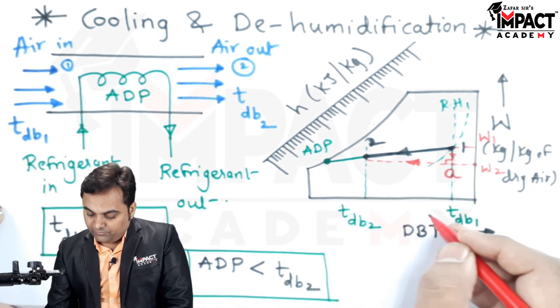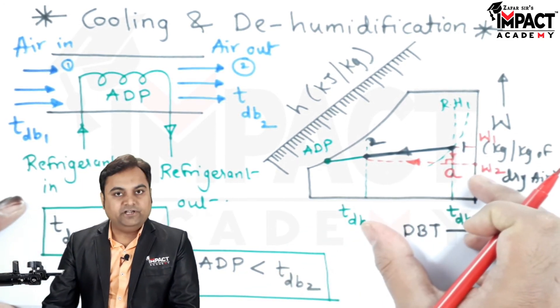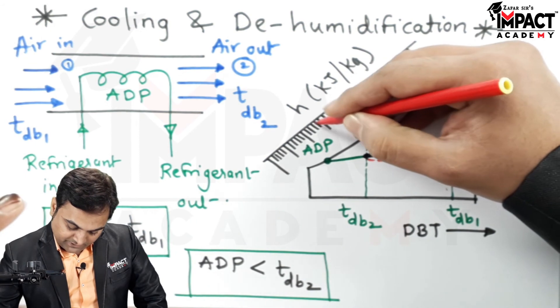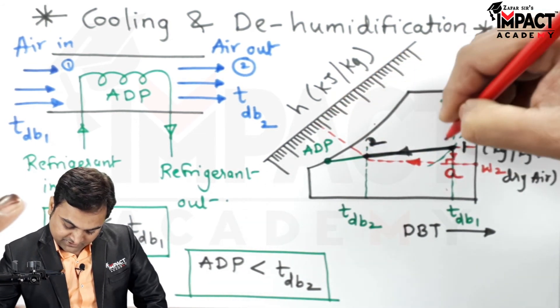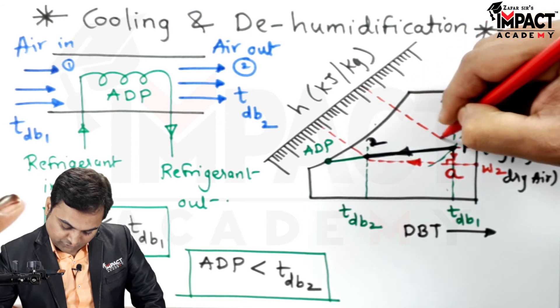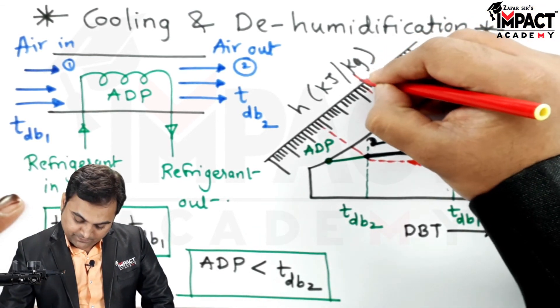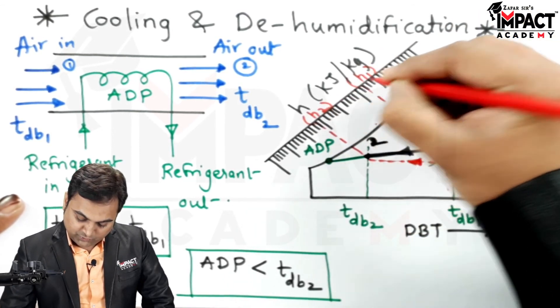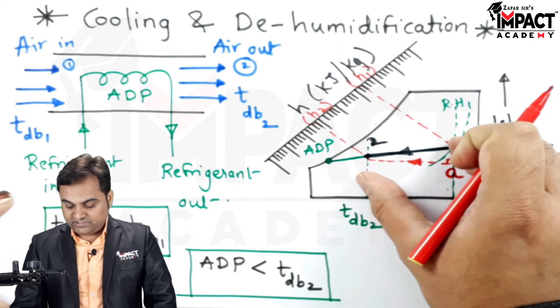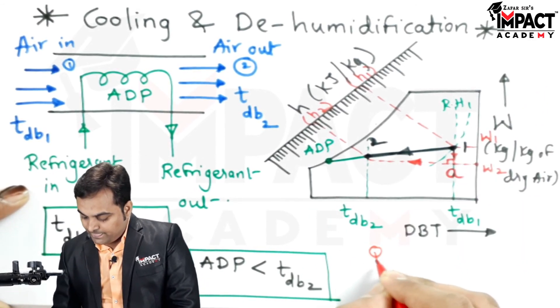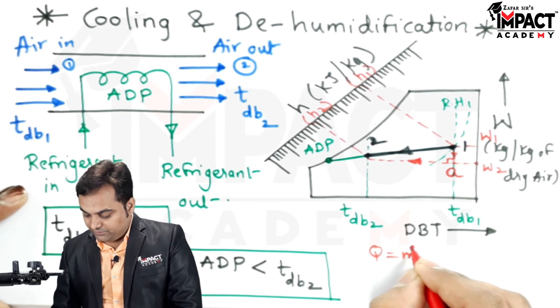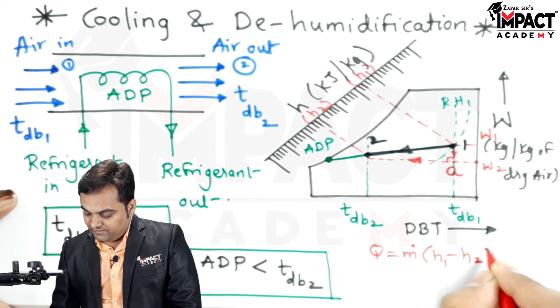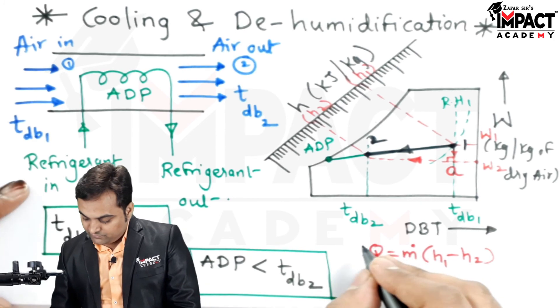The amount of heat removed from the air can be found by projecting the points onto the specific enthalpy lines, which directly gives us the heat removed. Here we have h1 and h2, so h1 minus h2 gives the amount of heat removed during the cooling and dehumidification process. This is multiplied by ṁ, the mass flow rate of air, and the specific enthalpy difference h1 minus h2, giving a result in kilowatts.